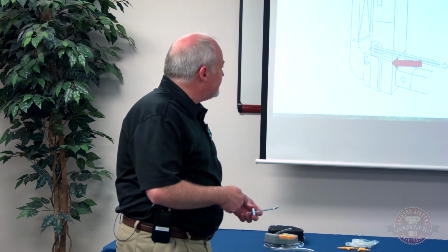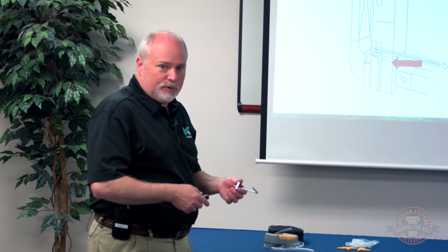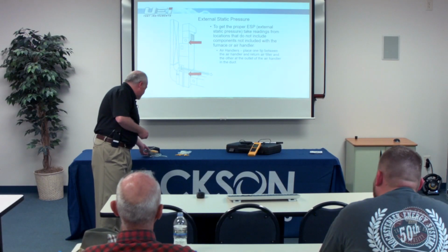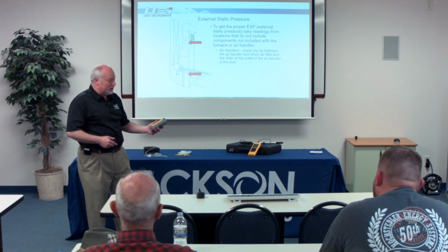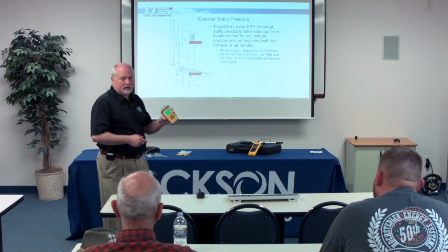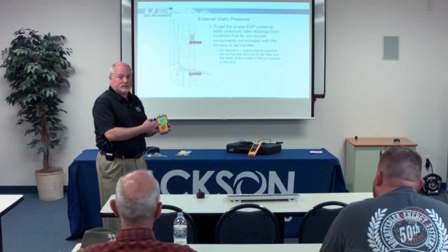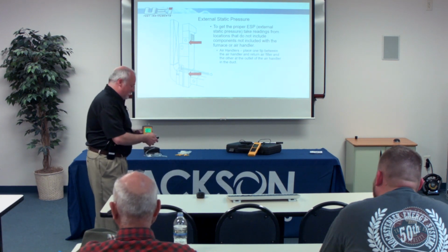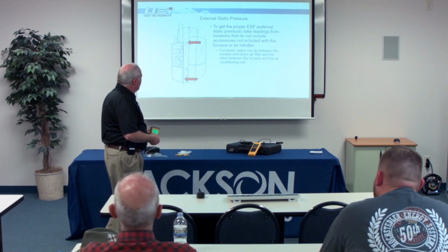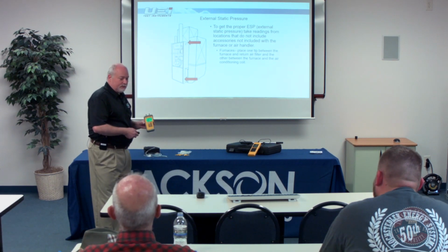If we put these on the supply and the return, and we put the one in the return on the negative side of our dual input manometer, and the one in the supply on the positive side, then our math is done for us. Okay? We don't have to do anything. All we do is read our number, and it's going to give us the information.